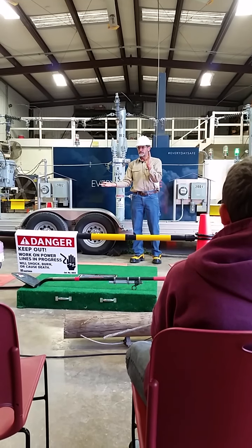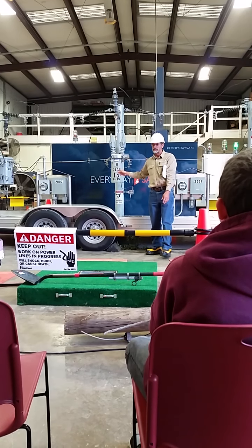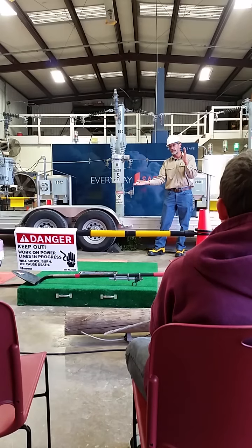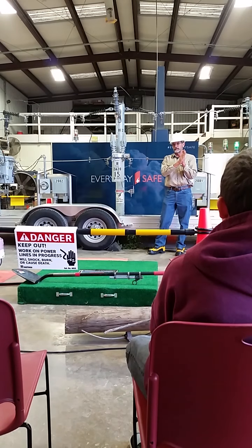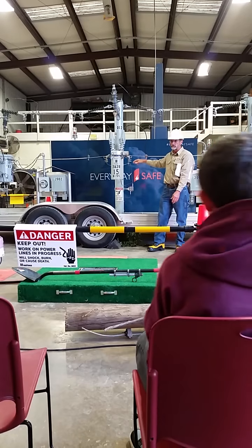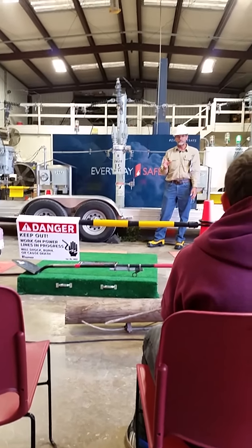But guess what, guys and ladies? That happens right about 85 to 90% of the time. This is a mechanical device. It's a hydraulic device. It can have trash in the oil. Those breakers have been known to open, close, and sit there open for 30 minutes and close back. Or just keep on cycling. I've seen that too. We had one breaker one time that I'm aware of that the handle would come down on it. They could bump it with a hot stick and it would close. It was just a malfunction.